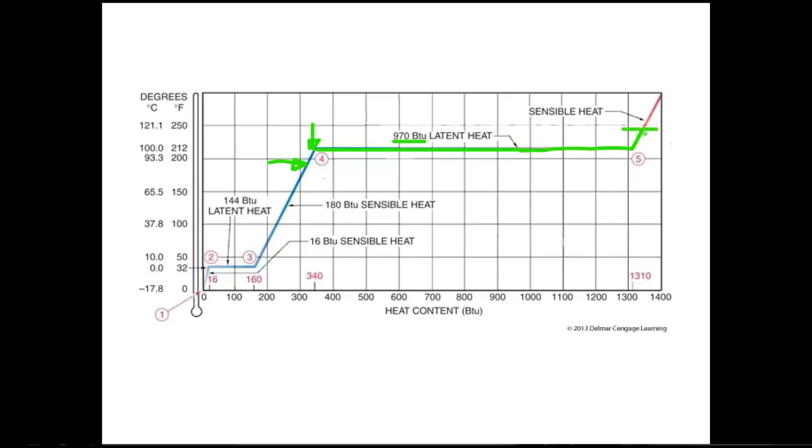At that point, it hits the compressor, it gets compressed, and the first part of the condensing coil desuperheats, removes the heat. We hit the saturation point. It comes back down as it condenses back down from the saturation point into 100% liquid, goes through the evaporator, or the condenser, and it becomes subcooled liquid again. Then it hits the metering device, goes back through the evaporator coil, and that is our refrigeration cycle.